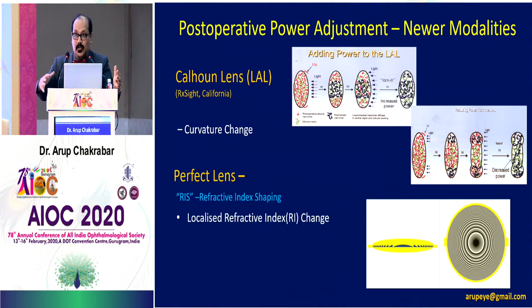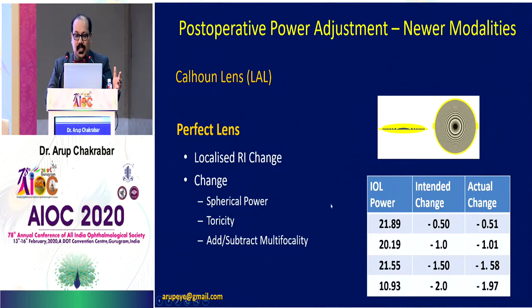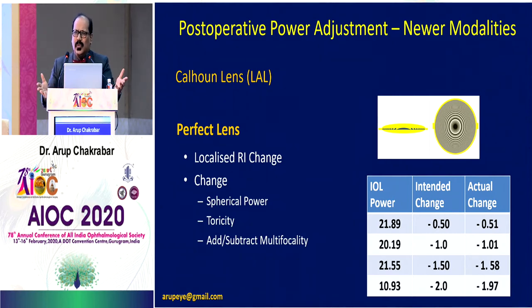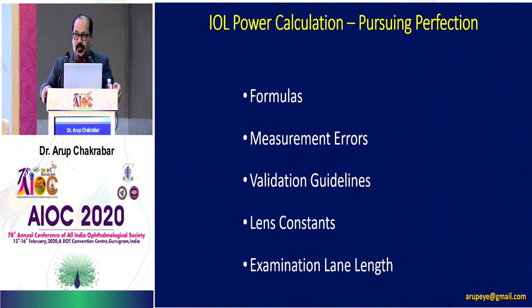Another technology that is coming up but not yet humanized is a femtolaser platform-based technology from a company called Perfect Lens — refractive index shaping. Using femtolaser light, refractive index changes are brought about within the substance of the lens. You can add or subtract spherical power, add or remove toricity, or even add or subtract multifocal qualities. However, even when these things become reality, they may not be critical in day-to-day practice because they are technology-based solutions that cost money and require repeated patient visits. So IOL power calculations still play a very important role.